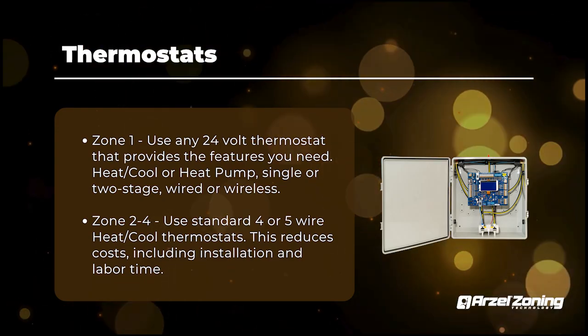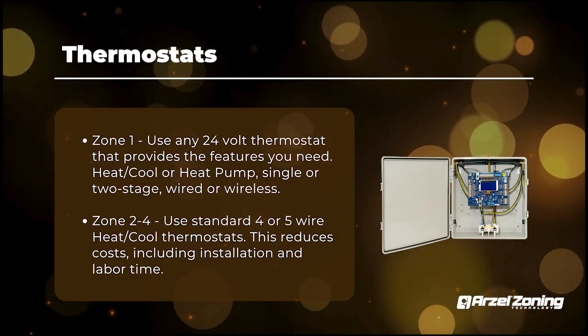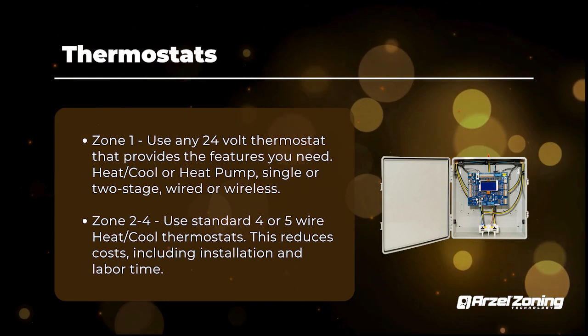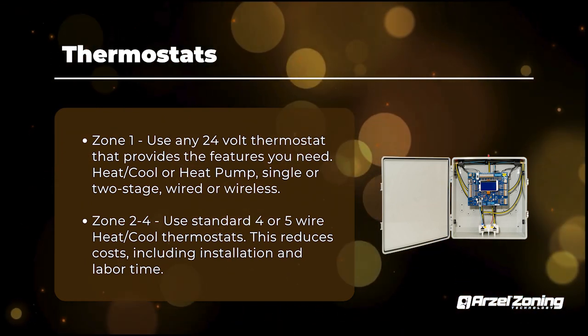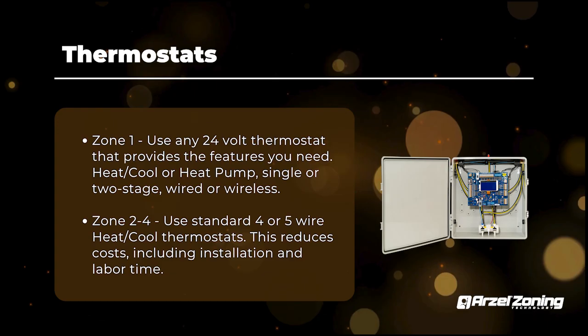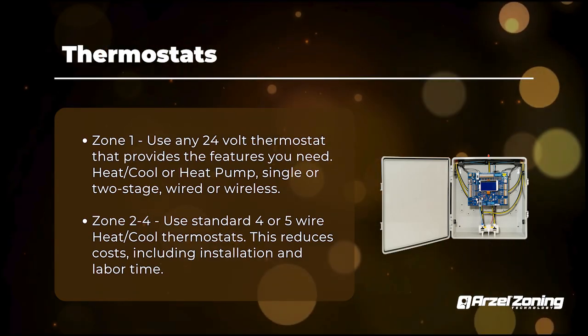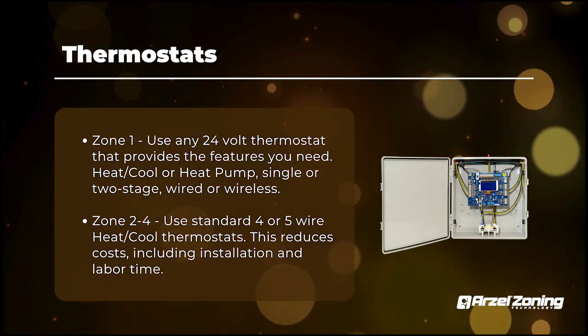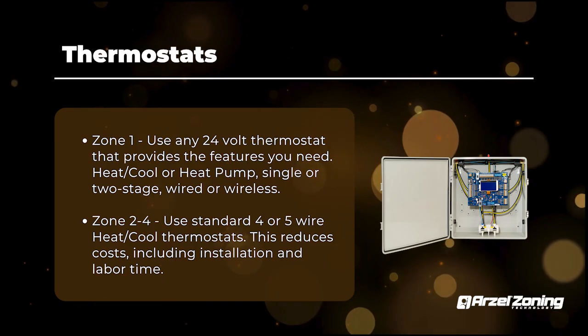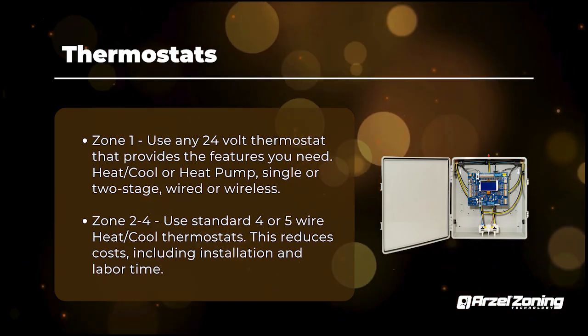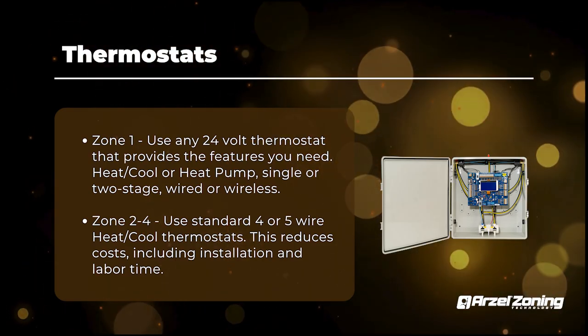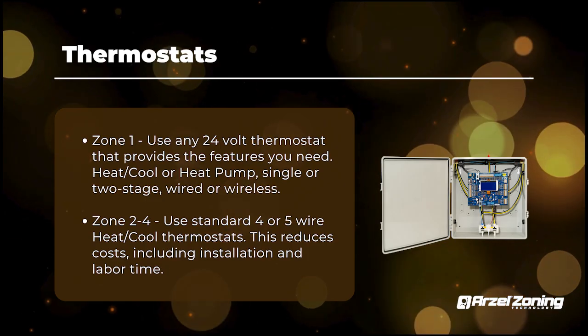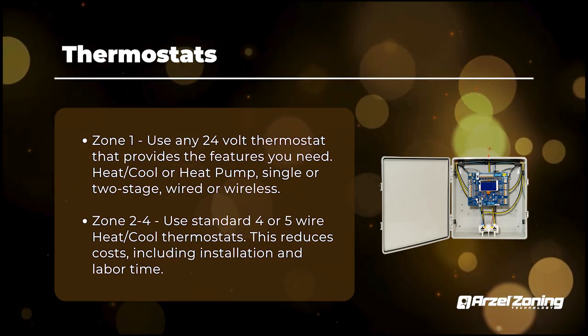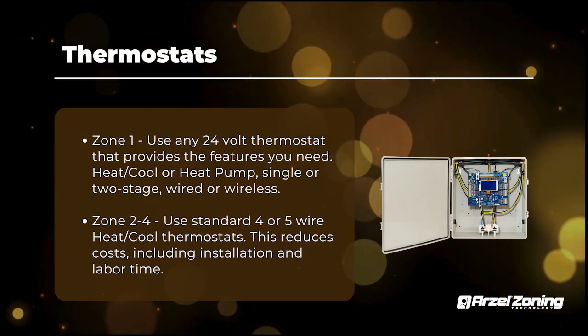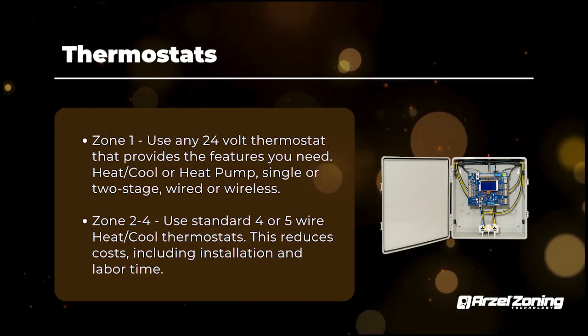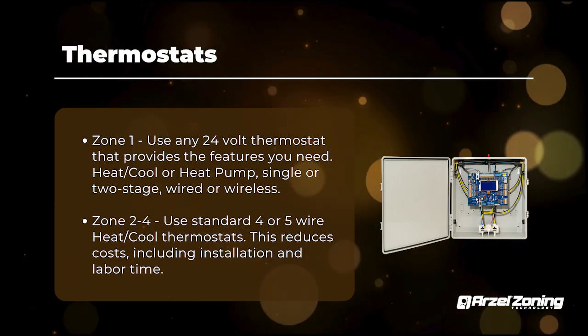Also with your zone 1, you can use just a heat cool thermostat on that zone as well. There's no need to use a heat pump stat, even if you're doing heat pump or dual fuel. The only thing to keep in mind is if you use a heat cool thermostat, make sure there's a setting in your setup wizard, which will ask you what your zone 1 stat type is. If you use a heat cool thermostat, make sure you reflect that in the setting. If you use a heat pump thermostat, make sure it's set that way. Otherwise, the panel will not respond to the calls. So you can do it either way on either application.